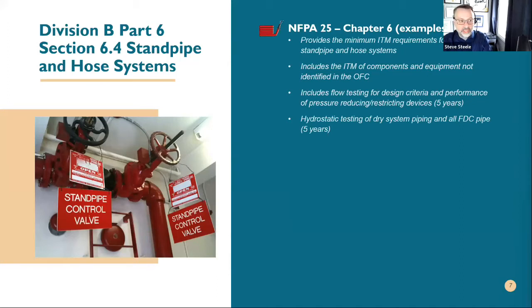So I know with the OREGs that change, and I know the advocating of the fire service to get that in there, that's a big problem in Ontario, and this would encompass or allow that for the 5 years as well. Main drain tests, what I've mentioned, so you're ensuring control valves, status testing, what condition that system is going to be in. So at bare minimum, an annual function is to say that somebody qualified and competent has checked off that system will run and perform as needed on an annual basis as well.